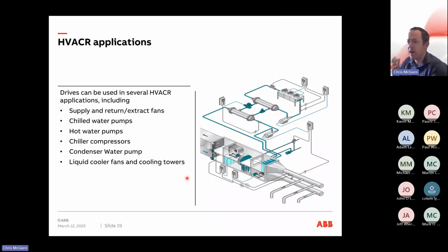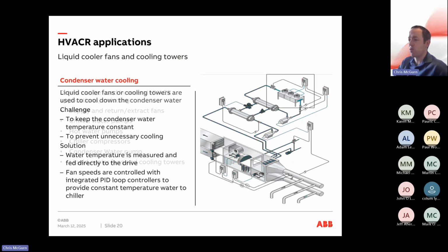So a little bit about HVAC-R applications. What applications are drives typically used on? We see them on many things. Like I say, fans and pumps tend to be the biggest: supply and return fans, chilled water pumps, compressors, cooler fans, cooling towers. They tend to see a benefit from using a VSD where part load is important for the actual running of the system itself.